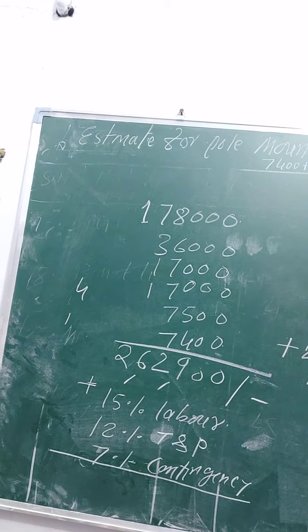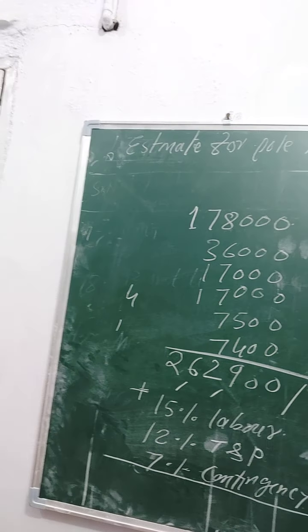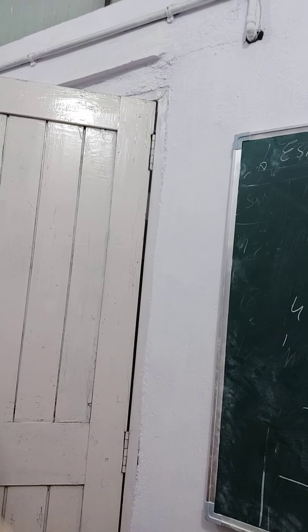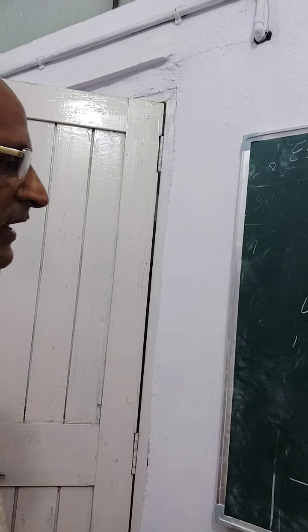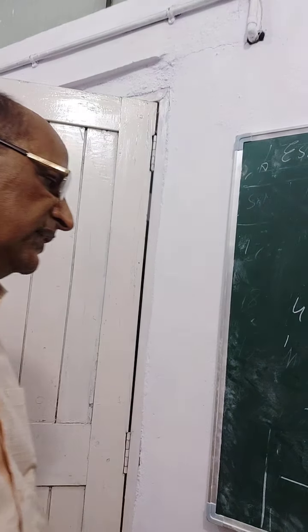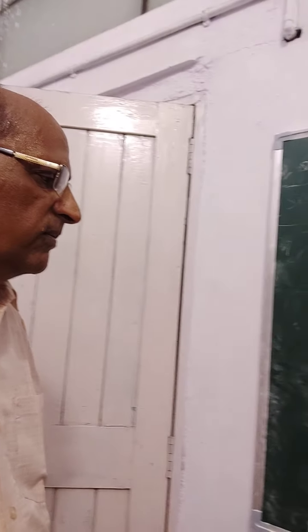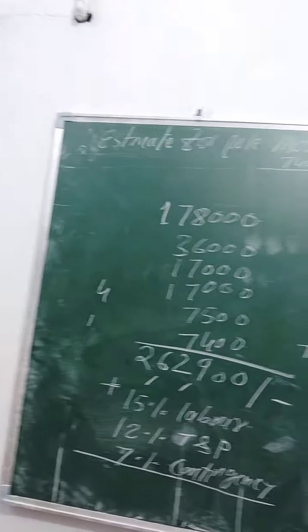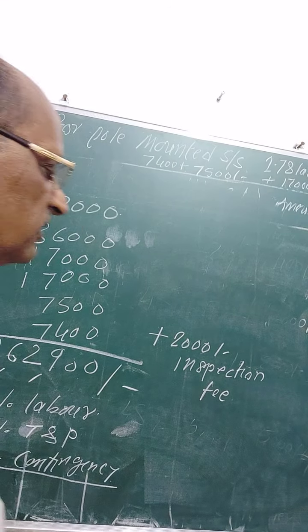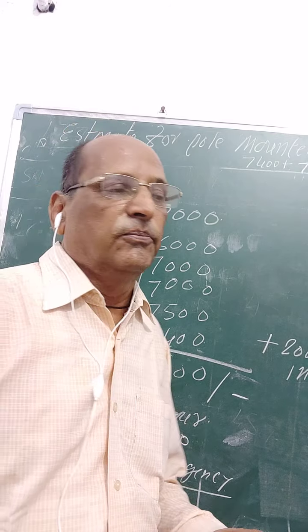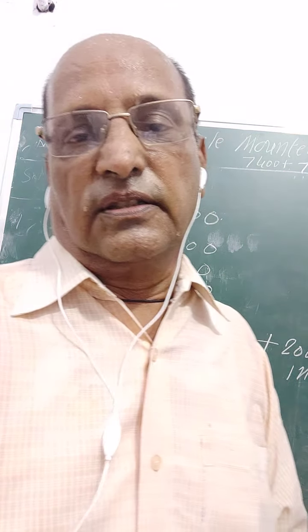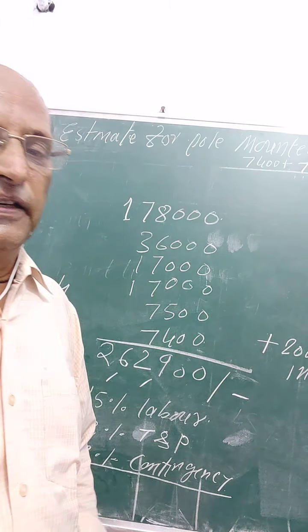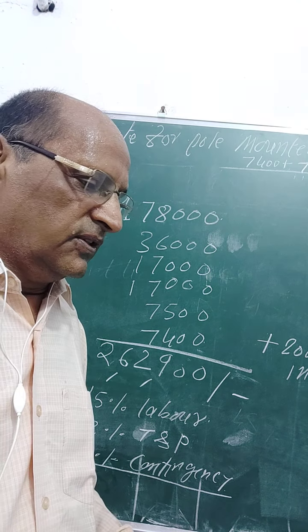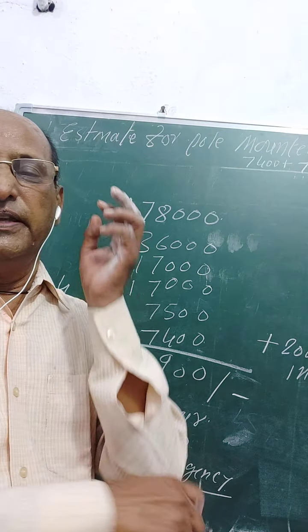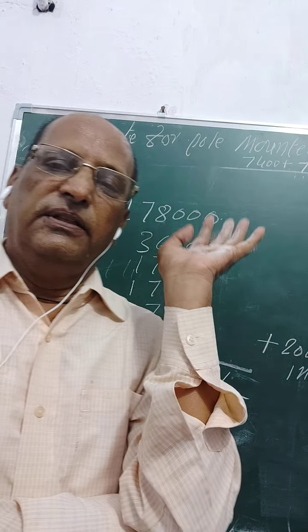So total estimate of this pole mounted substation of 200 kVA transformer 11 by 0.4 kV comes out to be 2,62,900 rupees material cost. On material cost you are taking 15% labor, 12% T&P and 7% contingency charge, plus 2,000 rupees inspection fees. So this will complete the estimate. You can find out the total cost. So one problem I have taken, any type of problem that comes in this pole mounted substation will only change the kVA rating of the transformer.